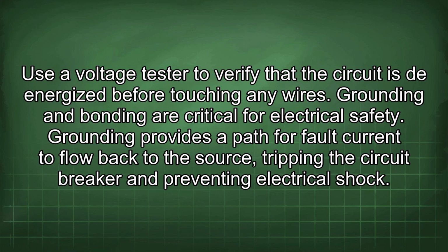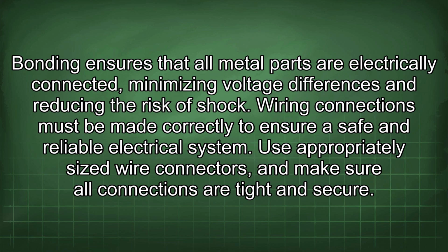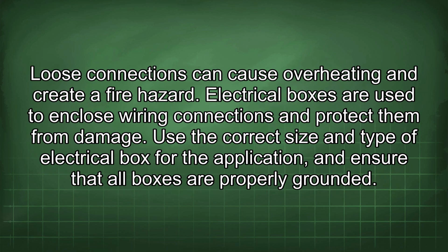Grounding and bonding are critical for electrical safety. Grounding provides a path for fault current to flow back to the source, tripping the circuit breaker and preventing electrical shock. Bonding ensures that all metal parts are electrically connected, minimizing voltage differences and reducing the risk of shock. Wiring connections must be made correctly to ensure a safe and reliable electrical system. Use appropriately sized wire connectors and make sure all connections are tight and secure. Loose connections can cause overheating and create a fire hazard.